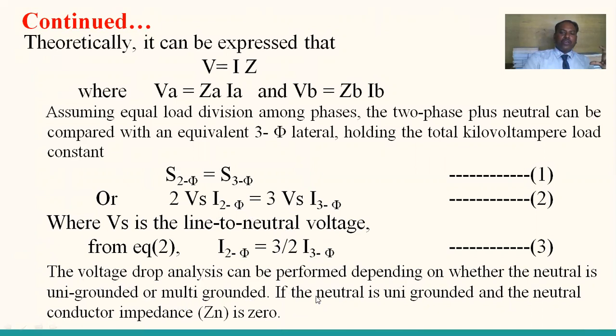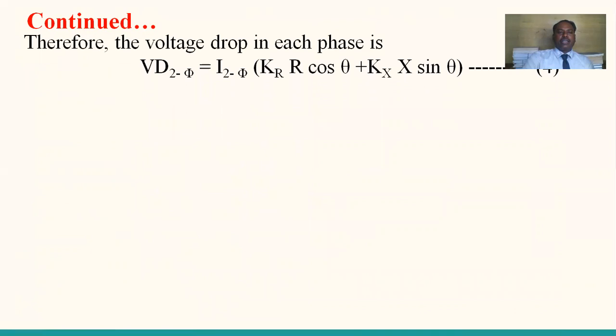So if the neutral is uni-grounded and the neutral conductor impedance Zn is 0, remember this point, otherwise it is greater than 0. Therefore, the voltage drop in each phase, all the systems are compared with the three-phase balanced system. There are conversion constants that come into the picture. Voltage drop of a two-phase system is equal to I2 phase into Kr into R cos theta plus Kx into X sin theta.